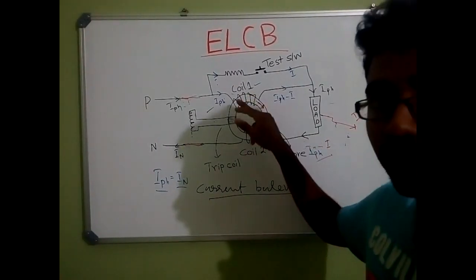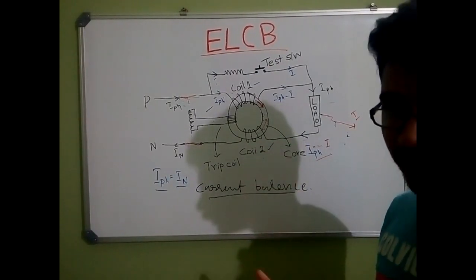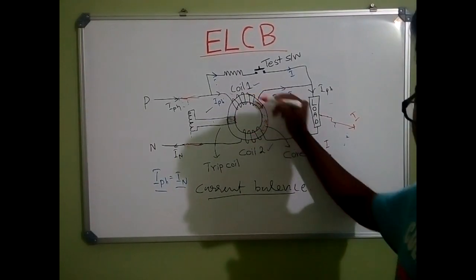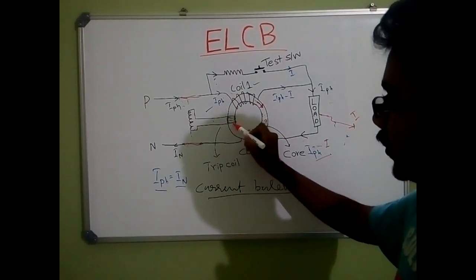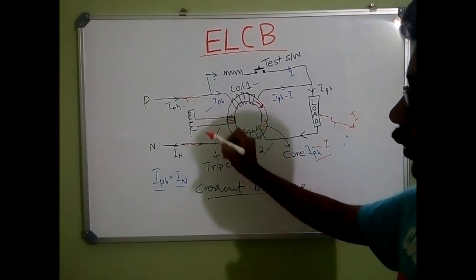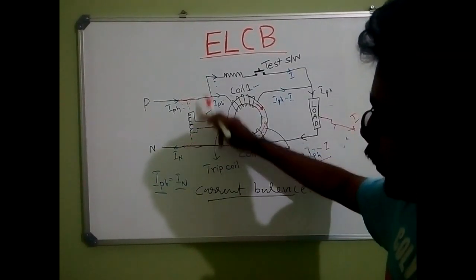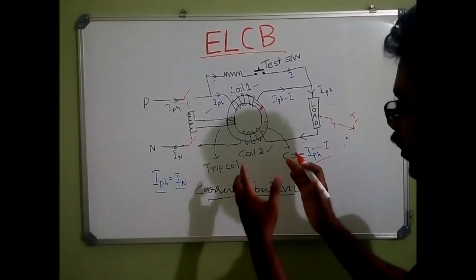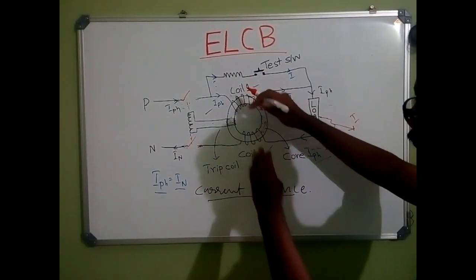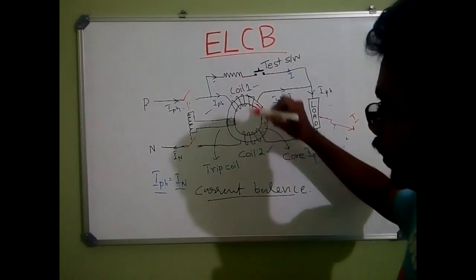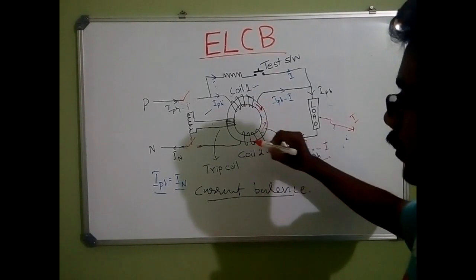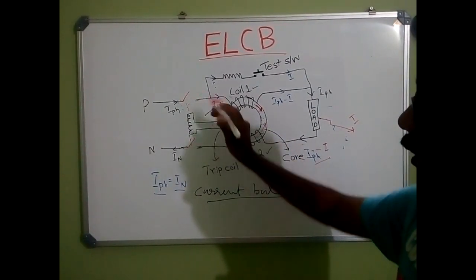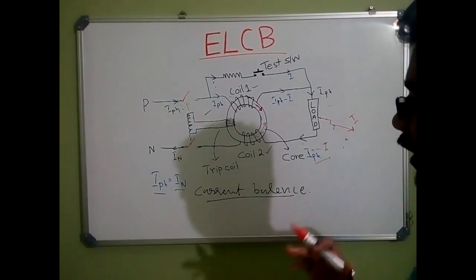The MMF produced by Coil 1 and MMF produced by Coil 2 are different. So there exists a net MMF in this magnetic core. Due to that net MMF, an EMF is induced in the trip coil, and through some mechanism, the switches are open-circuited by the trip coil. When leakage current happens, the current is unbalanced, so the net MMF activates the trip coil and isolates the supply from the load. This is how an ELCB works.